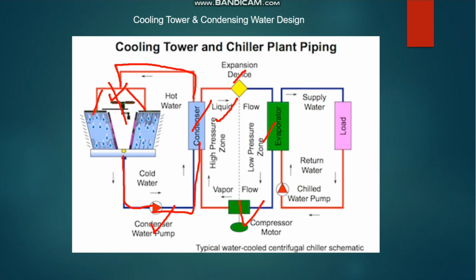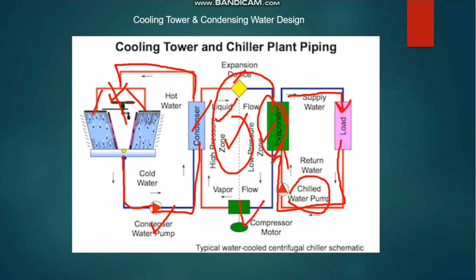Coming to the closed loop system, in the chiller, we have the chiller here. From the chiller, the cold water is supplied to the load, which can be AHU, FCU and different HVAC equipment used in the building. After that, the hot return water comes back to the evaporator using the chilled water pump, and at this point the heat exchange happens. So this circuit keeps on running.